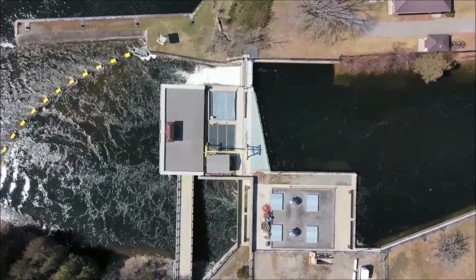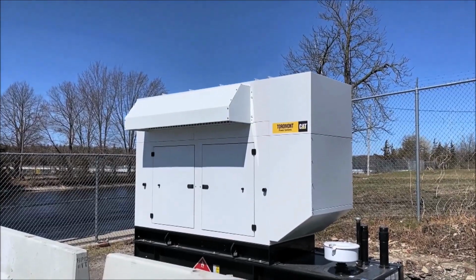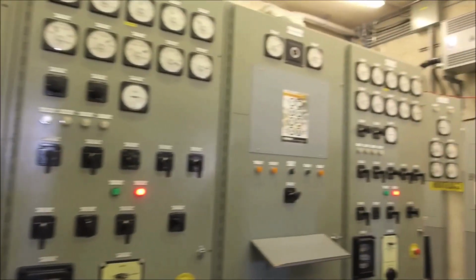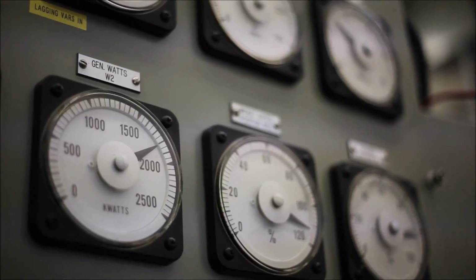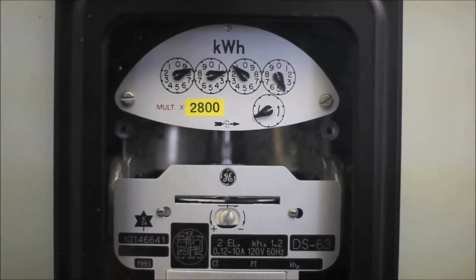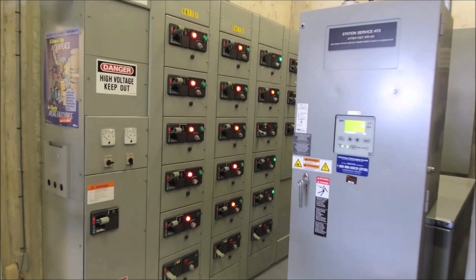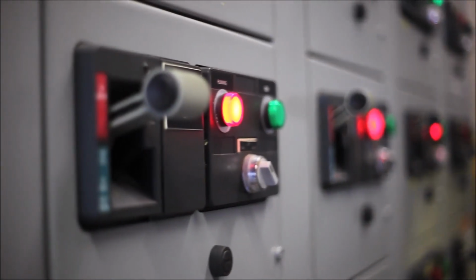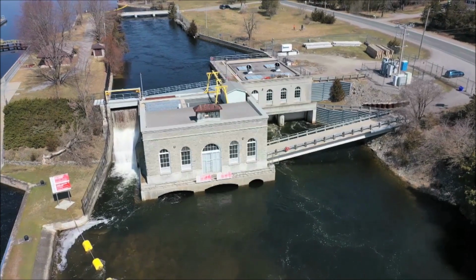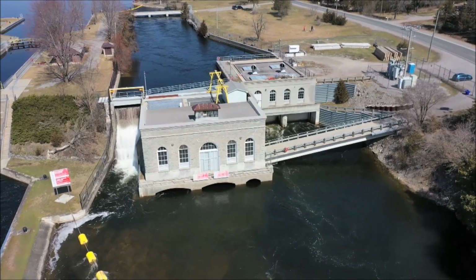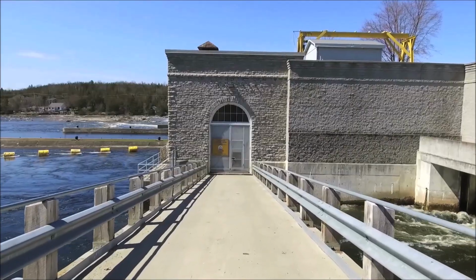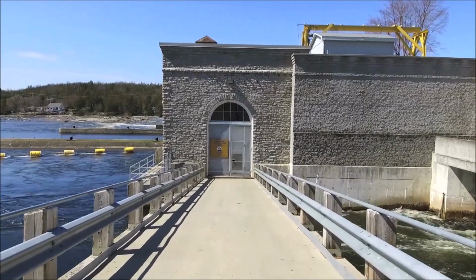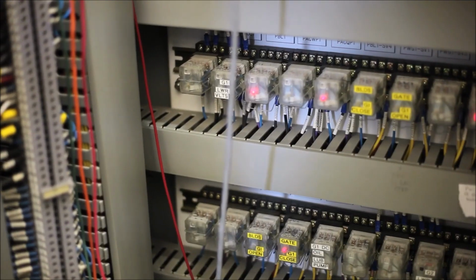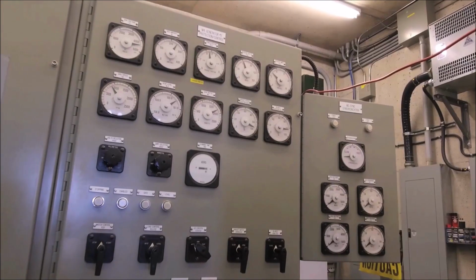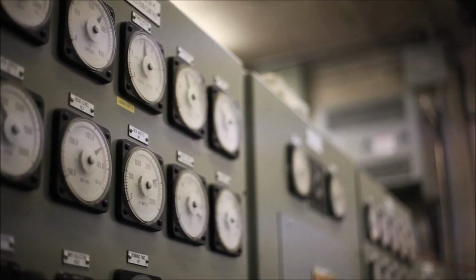At the end of 2020, we also installed an 80 kilowatt backup engine. The engine supplies the Master Control Center located in Plant 2, which also supplies Plant 1 station service. Based on the interconnection, before the backup engine was installed, an outage at Plant 2 would also require the shutdown of Plant 1. We are now able to continue running Plant 1 even if the grid connection to Plant 2 goes down.